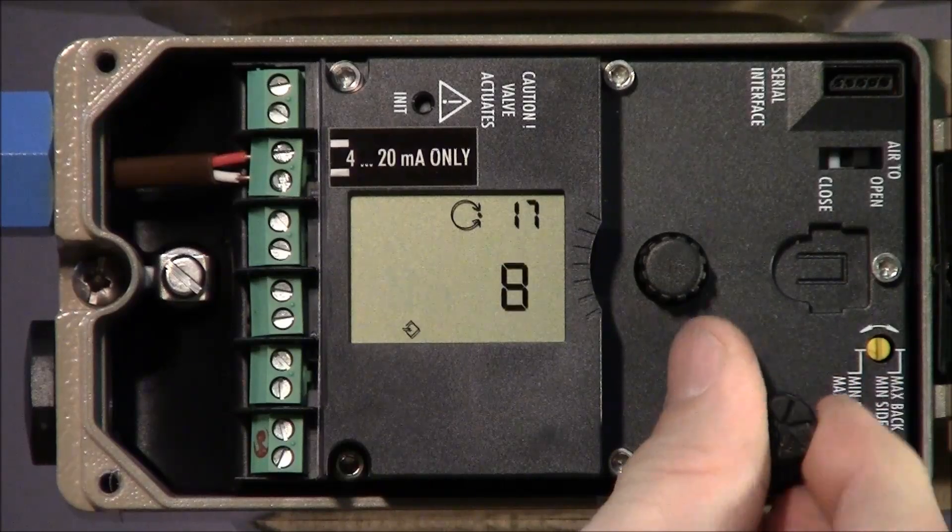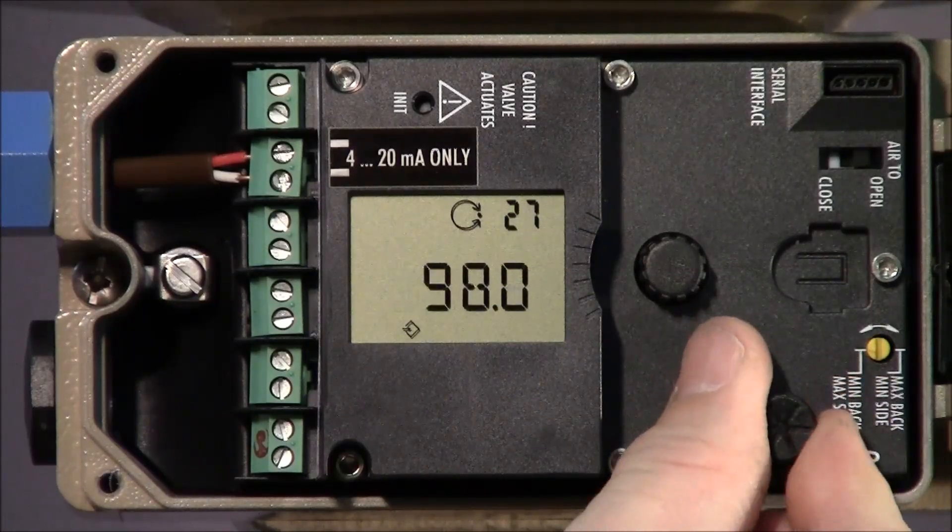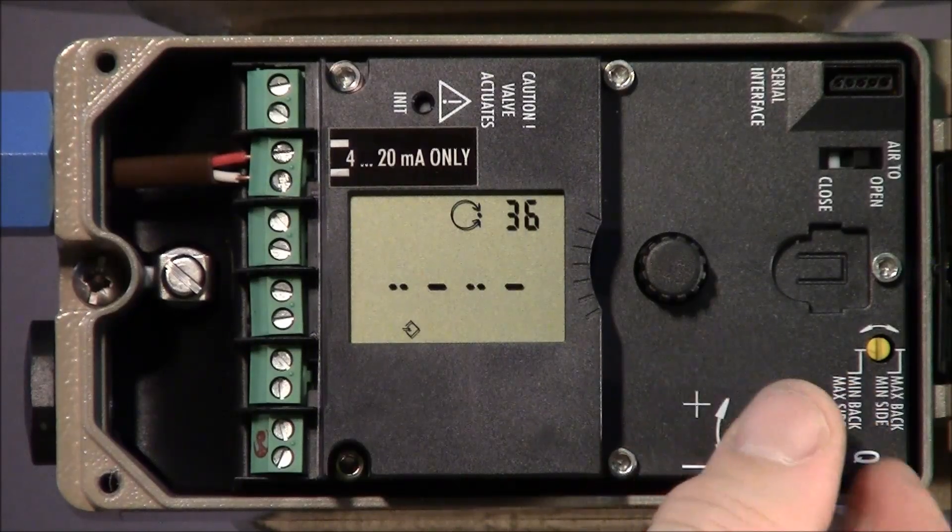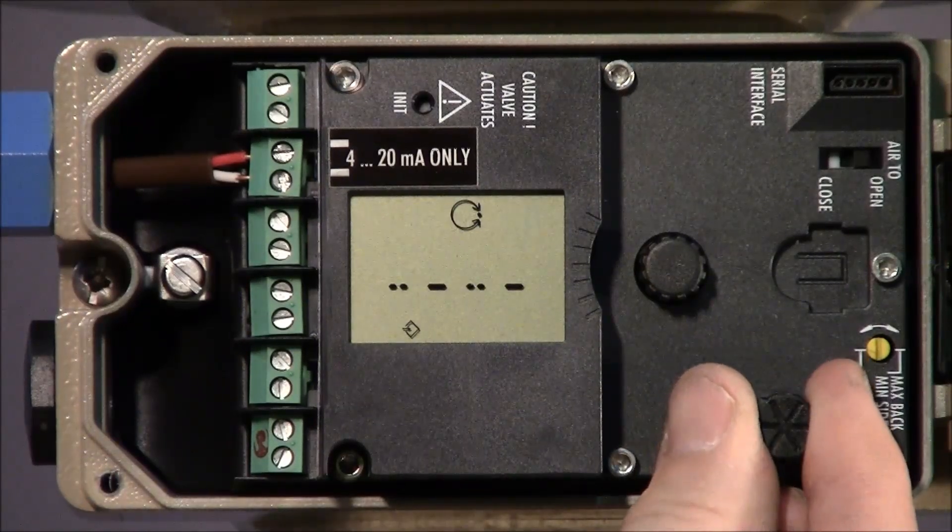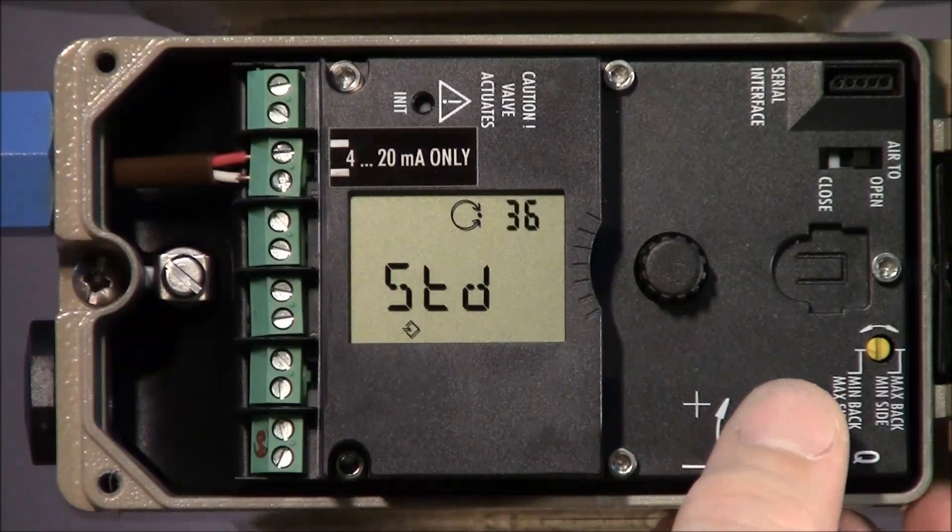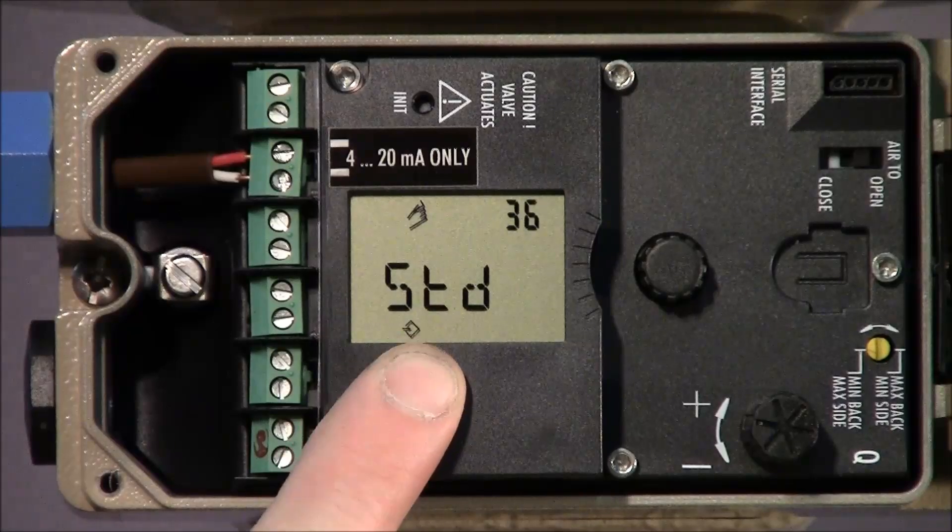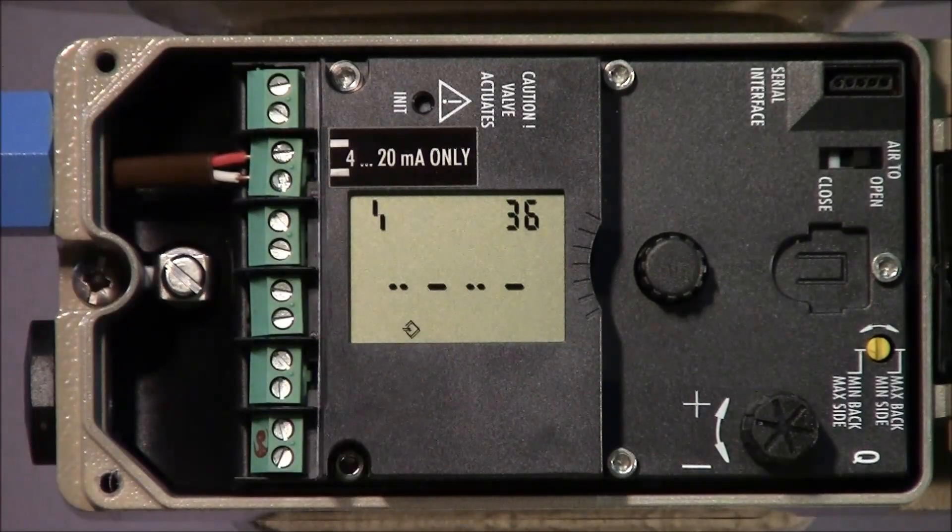Now, we'll go to parameter 36 to reset the positioner to factory defaults. Push the knob and then rotate until it indicates standard and push once again. Wait until standard disappears from the display to complete the factory reset.